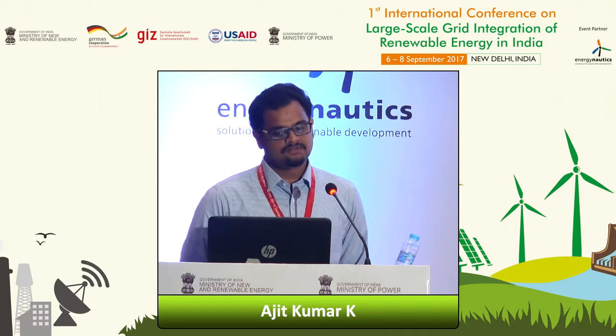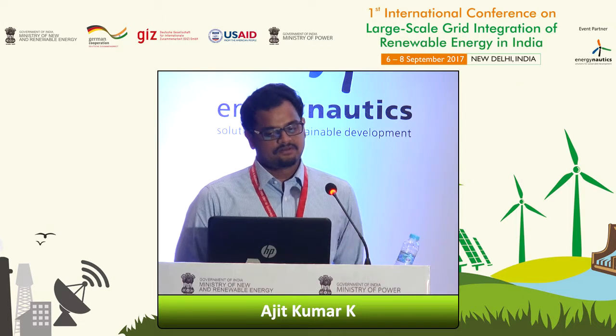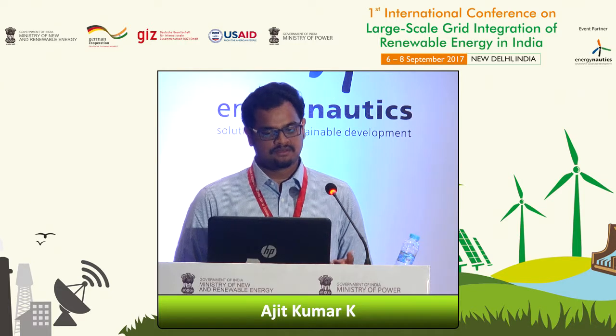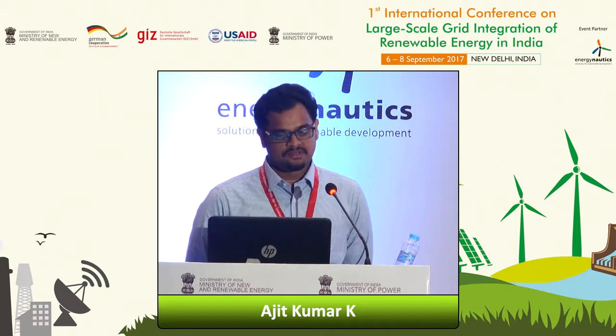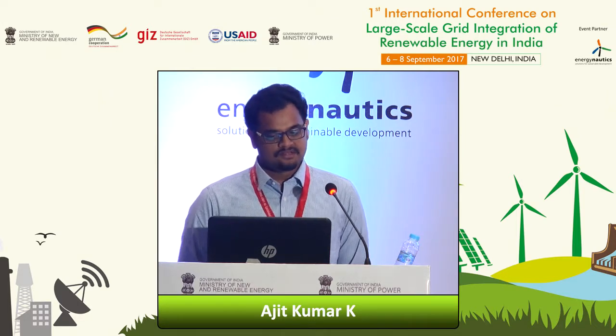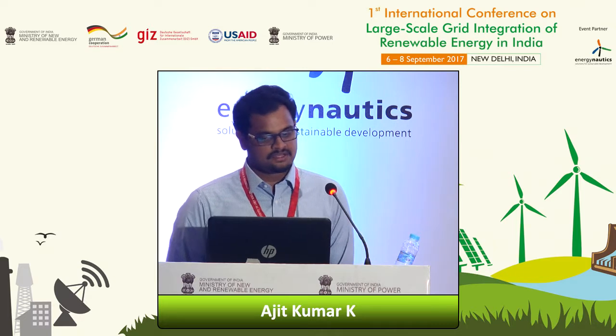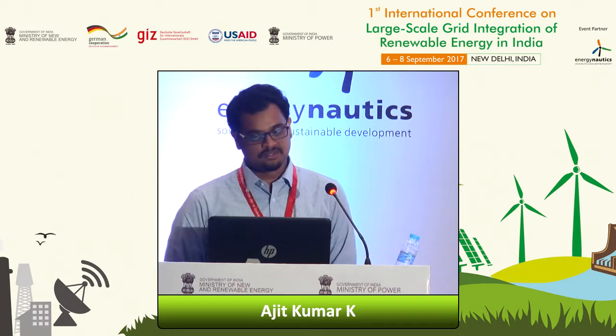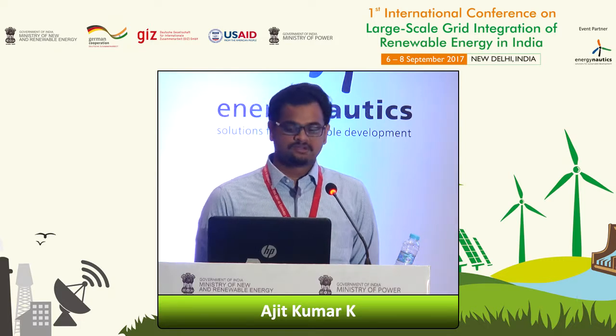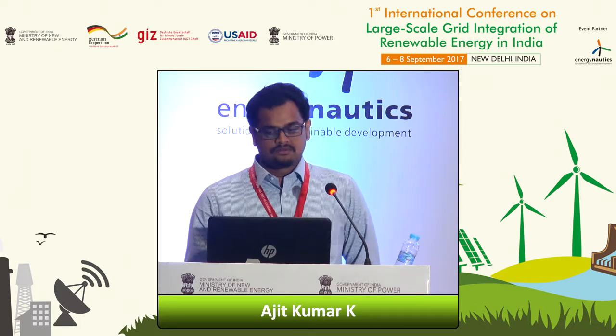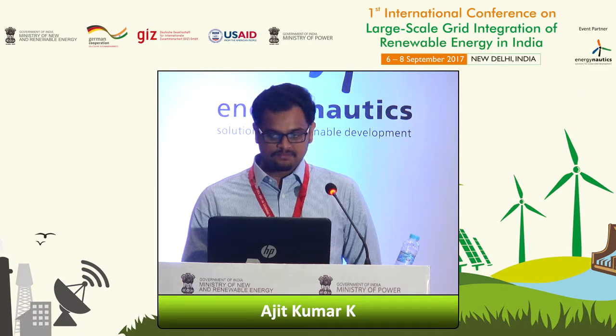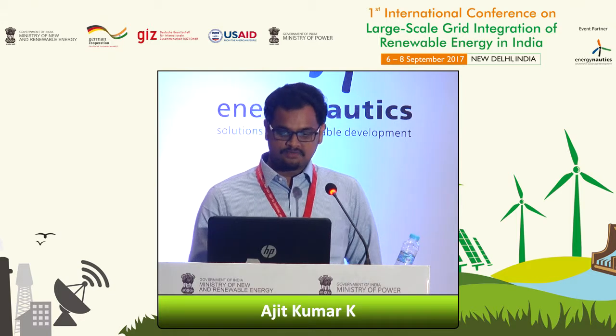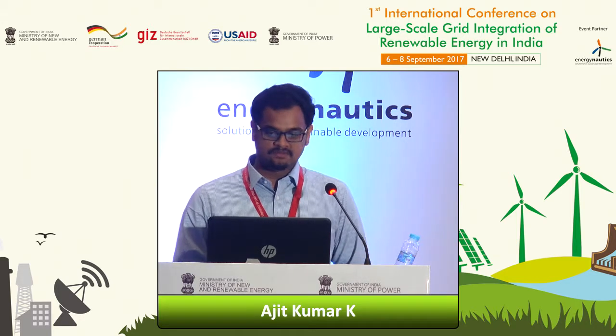The third transient case considered was the effect due to the loss of a transmission line. The post-fault performance is plotted. The oscillations were observed, and here also the same results were obtained, wherein for the 30% solar penetration case the oscillations were larger and not converging to a stable value, forcing the system to go out of synchronism. This is a voltage plot. Again, it was similar to the previous case.